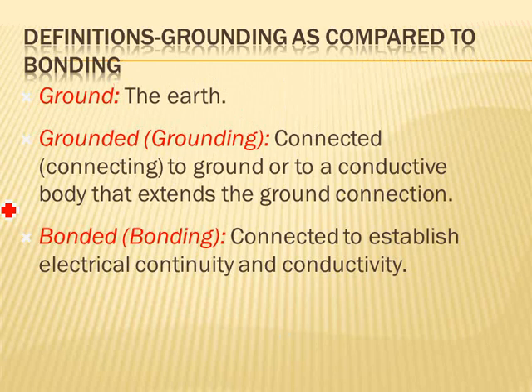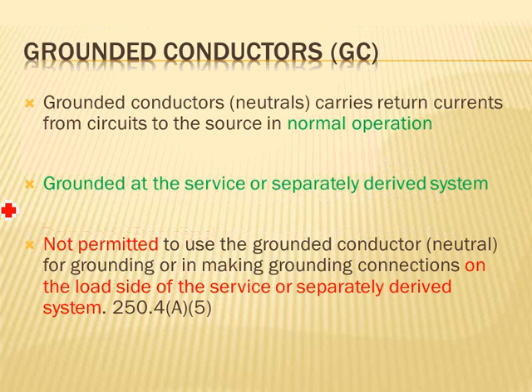So grounding and bonding almost give the same function. It becomes a big deal with a bonding conductor: you have a piece of equipment with a 20 amp circuit coming to it, so you bring hot and neutral to it, and you have an equipment ground conductor tied to, let's just say, I don't know, a fan in a tank, right? And the tank is also bonded to the frame of the fan. That's now we're bonding it together. So with a wire, we're taking an equipment ground conductor all the way back to the source.